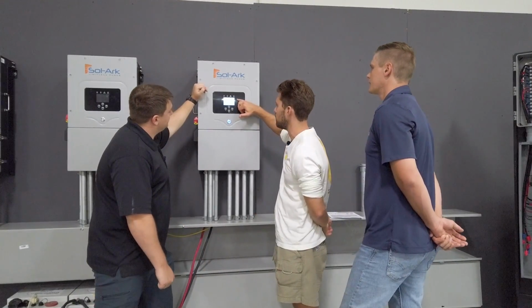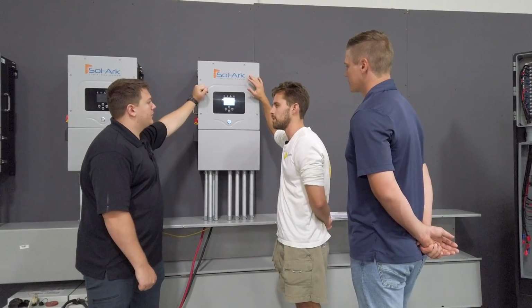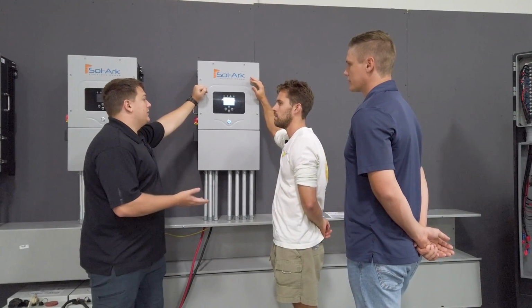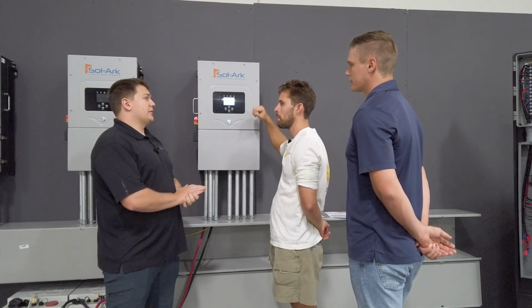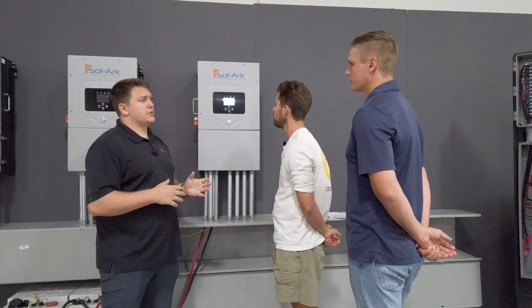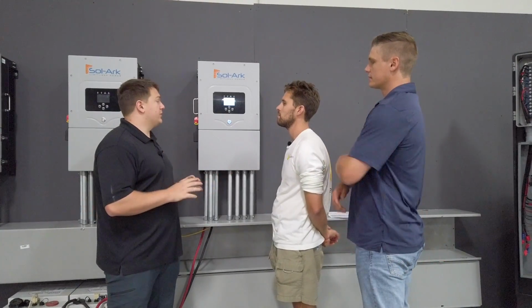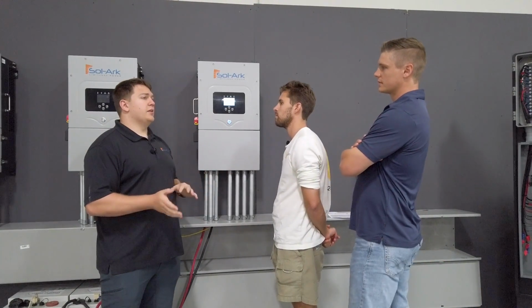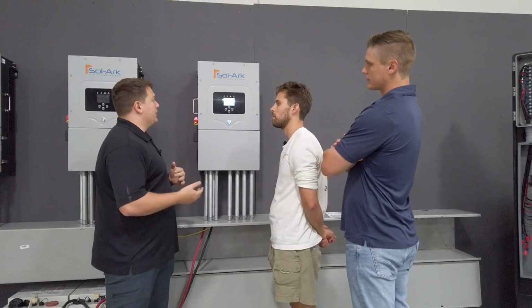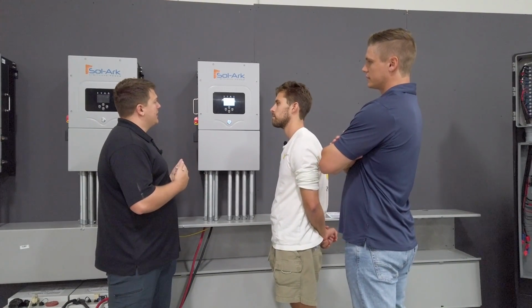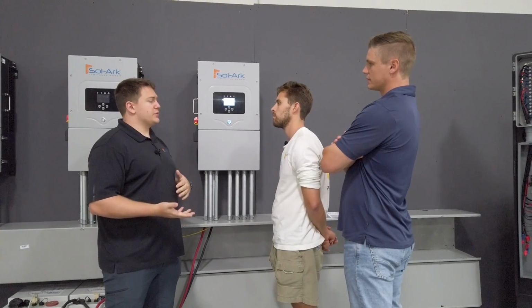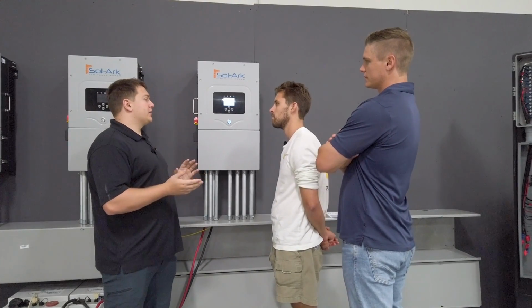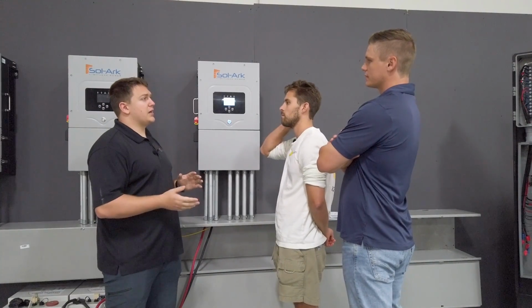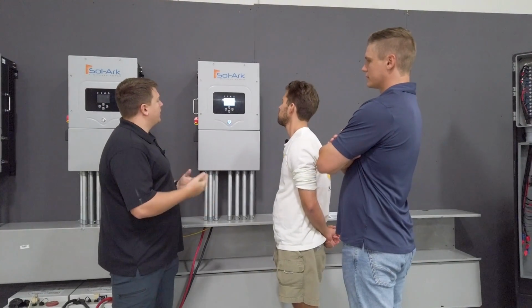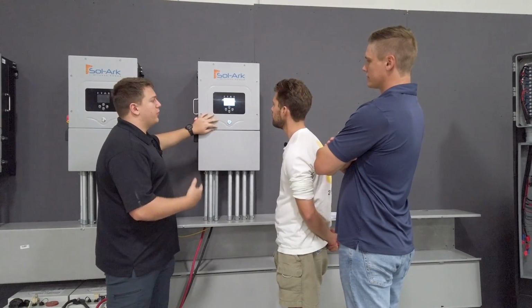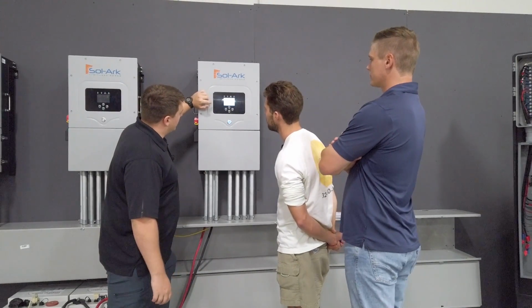Is it necessary to put these in? Would the system mess up if we didn't put them in? So potentially, yes, you could hurt the battery if you don't change these settings. These days, with all the latest software versions, units that have been shipping out for the last year or so, we've defaulted these settings to approximately lithium iron phosphate chemistry. We used to default to lead acid chemistry, but basically if you have a battery that isn't the default chemistry and you're using the default settings, it's probably not the end of the world in a day, but it would cause problems over time potentially. Again, you want to change this as part of the commissioning. So before you actually use the system heavily, you'll definitely want to change these things.